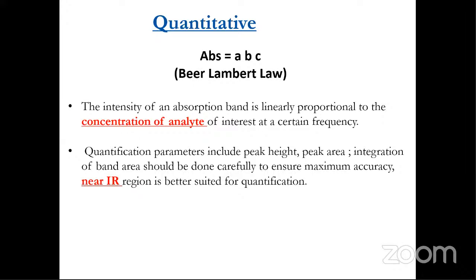Quantitative: based on Beer-Lambert's law, we also use the NIR spectrum, where the intensity of the absorption band is linearly proportional to the concentration of the analyte. Quantification parameters include peak height and peak area. Integration of the band area should be done carefully to ensure maximum accuracy. The near IR region is better suited for quantification, so we have to look at the frequencies in the near IR region, and set aside the mid IR and far IR regions for quantification.